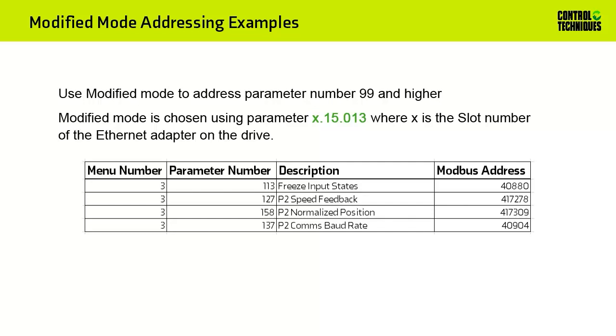Modified mode is used to address parameter numbers greater than parameter number 99. To use Modified mode, you must set parameter number 13 in menu number 15 of your Ethernet interface to Modified. In my example, I'm using a Digitax HD, so Modified mode can be changed by entering slot number 3, menu 15, parameter 13. If you're using a Unidrive M700, it is slot 4, menu 15, parameter 13. If you're using an SI Ethernet module, it would be slot 1, 2, or 3, depending upon where the SI Ethernet module is installed.